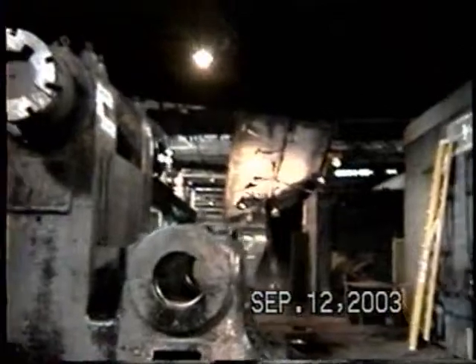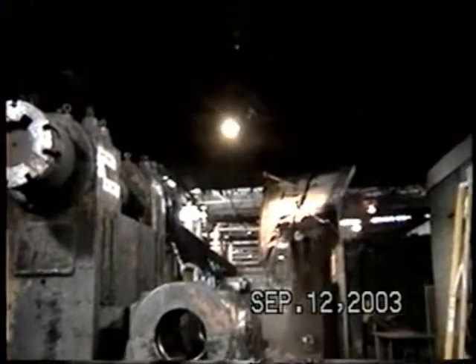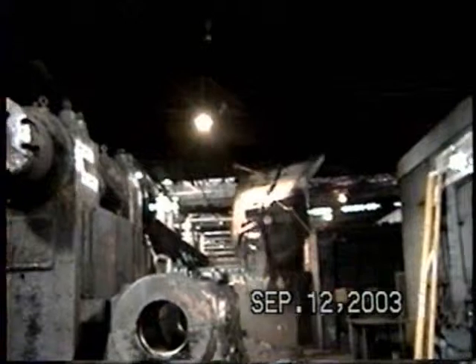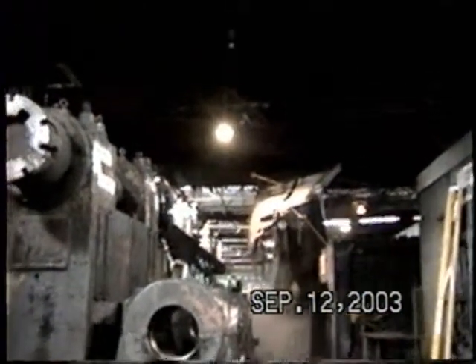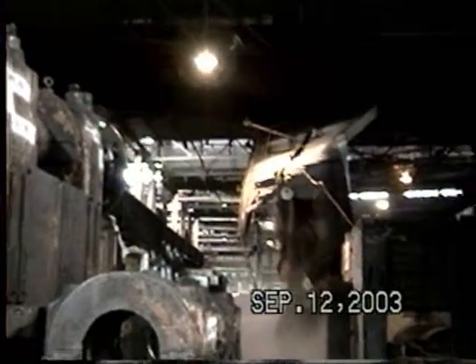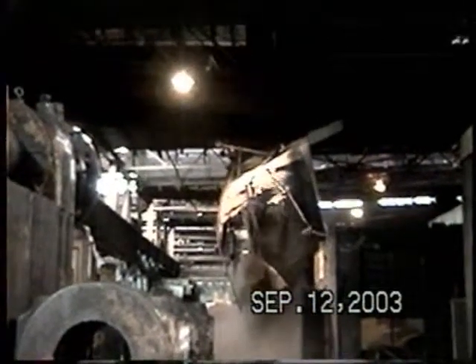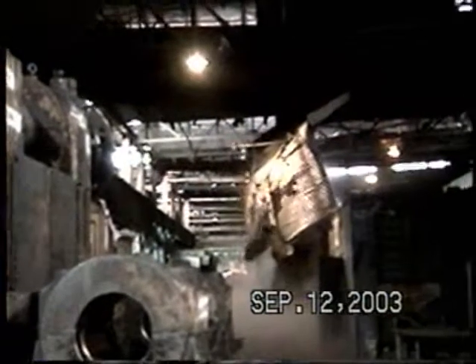The other guy pulled this down earlier. The roof fell on the motor room and the bus in there, the AC and the DC bus. Shut the rectifier down, shorted out a cable halfway down the mill that was resting on an angle iron. It fell off, and it finally went through completely with that surge. But the direct short left here.